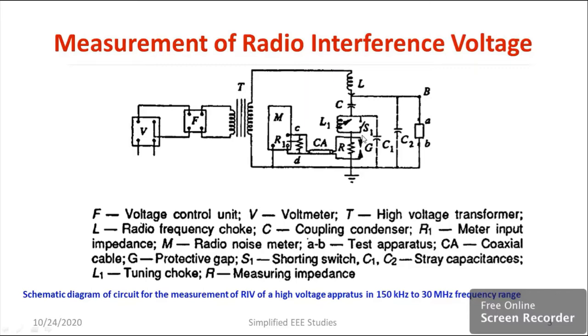We have one coupling capacitor, also called a coupling condenser, to connect different stages. Suppose some partial discharge takes place in the dielectric material. Immediately the signal will come across the particular resistor. That signal will be transferred to the radio interference meter with the help of a coaxial cable. From the meter you can see the range of signal — whether it is a high frequency signal or low frequency signal. Definitely if it is a high frequency signal, that will be the reason for radio interference.